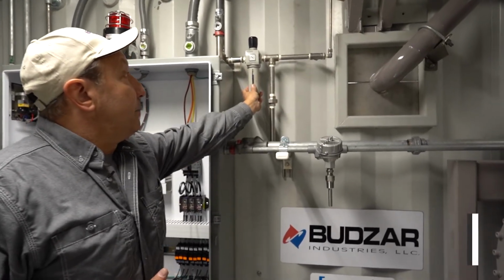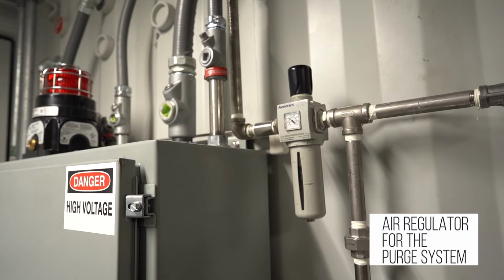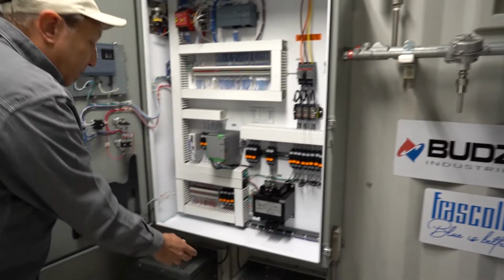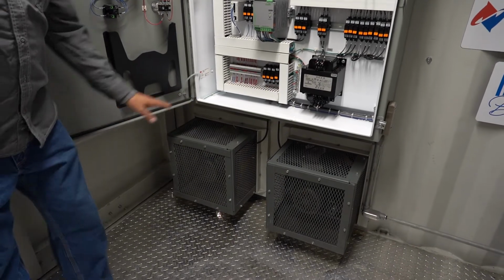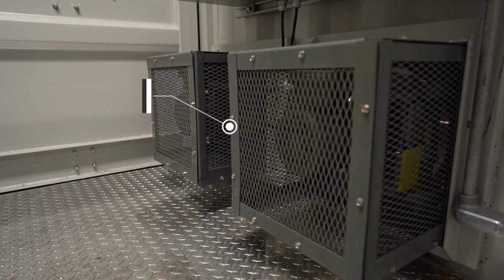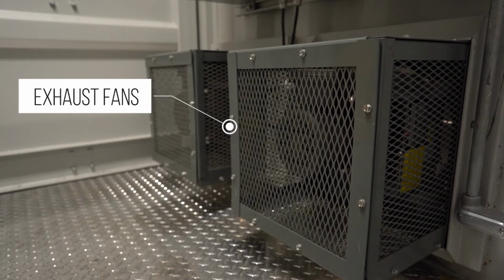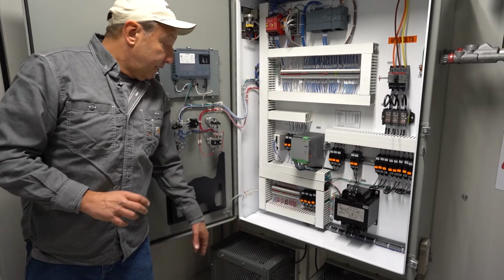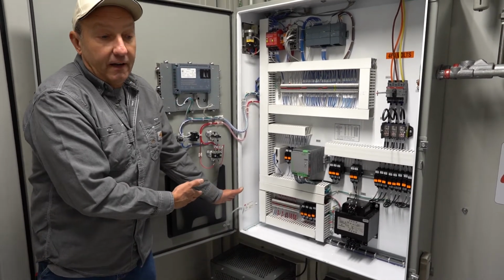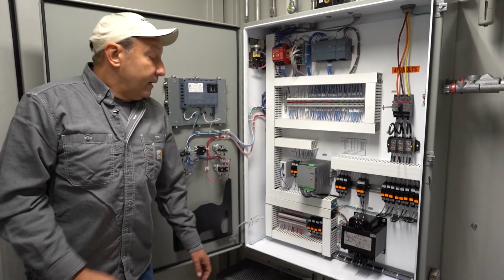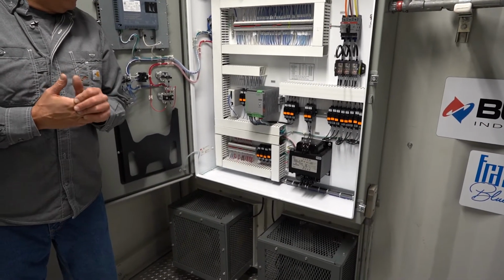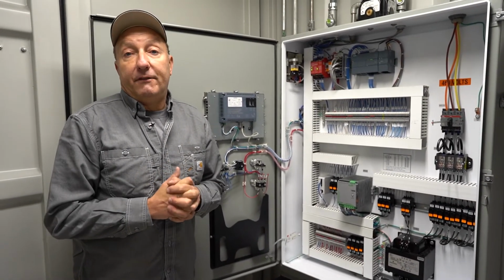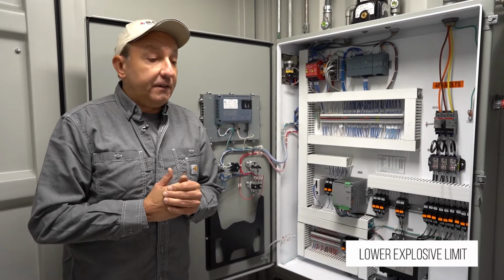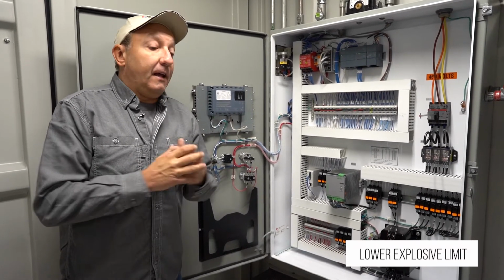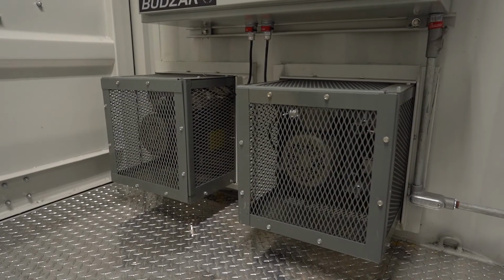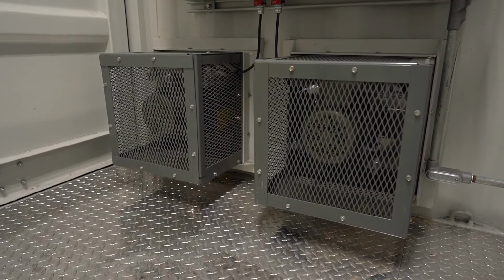This is our air regulator for the purge systems and for the block valves on the process loop that we reviewed earlier. Down below are our 2 exhaust fans. The one on the left runs just about 100% of the time. We have a cross flow. On the other side of the container, we have intake vents. So this fan is running and taking air from inside the container, exiting it outside, and we're bringing air in on the other corner. The other fan is utilized in the event of a propane leak. We have an LEL propane leak detection system, very nice system, and if that is tripped or senses propane, then the second fan comes on and we increase the flow through the container for safety.